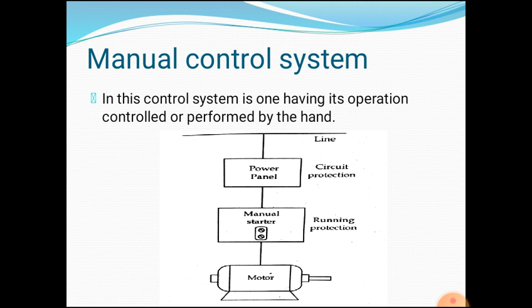A manual controller requires the operator to move a switch or press a button to initiate any change, like start or stop, in the operation of the machine equipment. Examples: woodworking shops, drill presses, lathes. This is the manual control diagram which consists of line, power panel, manual starter, motor, circuit protection, running protection.